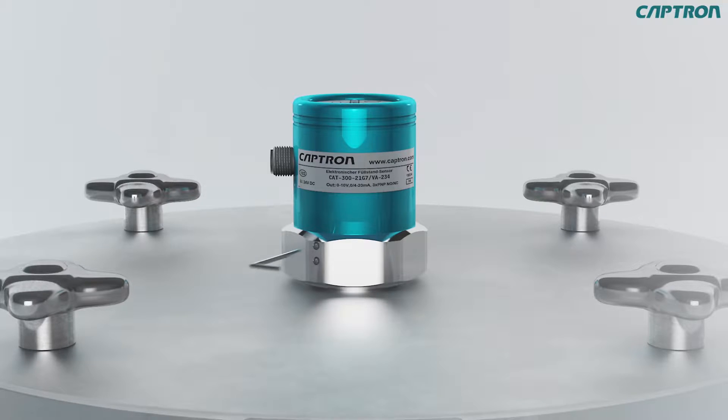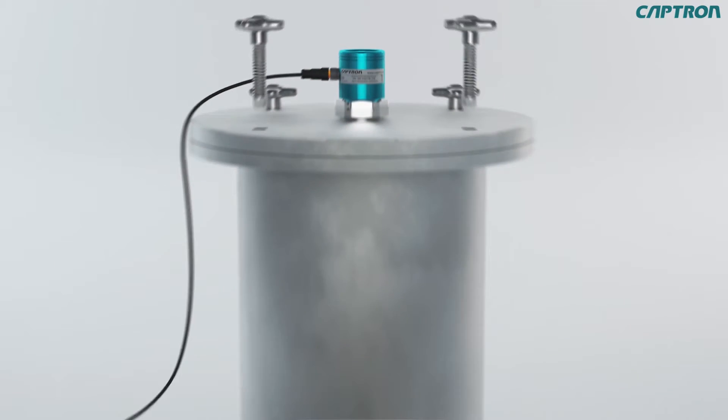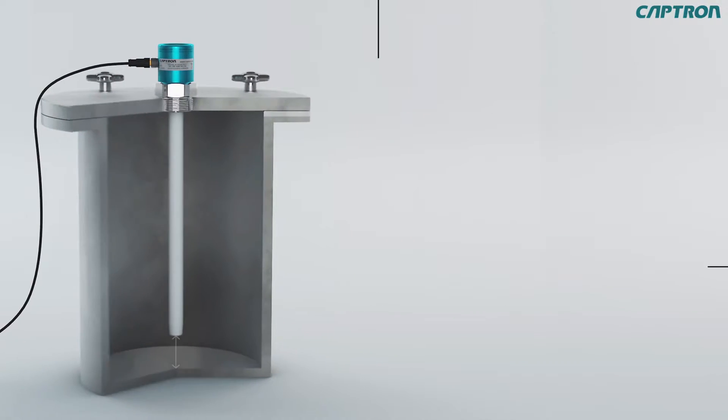Use a hexagon wrench to loosen the upper stud screw with two turns to the left. Once the probe head has been optimally positioned, attach the M12 cable socket to the connector. Make sure that the probe tip does not touch the tank bottom during the installation.